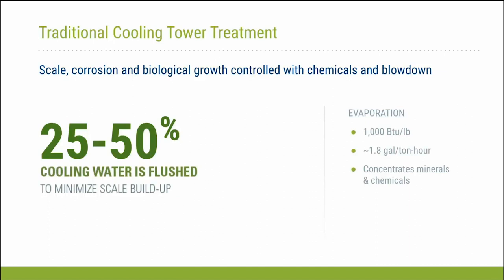These technologies, as Kevin mentioned, it's important. These technologies mostly save water. We actually look at water savings, chemical savings, and energy savings from these technologies and cases. The reason is, 25 to 50% of the cooling water is wasted in blowdown in these cooling water systems, depending on water quality and cycles of concentration and that kind of thing. Just as a rule of thumb, 1,000 BTUs to evaporate a pound of water, that's almost 2 gallons of water for every ton-hour of cooling at a site. So the water issue is getting more and more important.